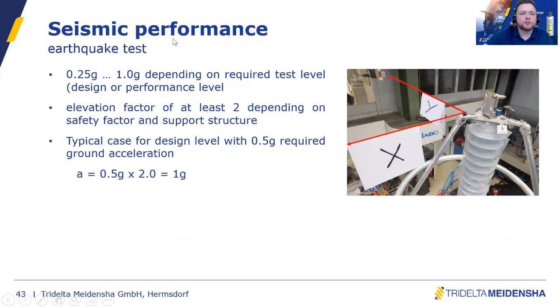Typically, this earthquake test is done with a ground acceleration between 0.25 G and 1 G, depending on the requested design or performance level. And we have to consider some factors, which are, let's say, security factors. At least we take 2. So we multiply the requested bottom acceleration by 2 or more. In a typical case, 0.5 G requested multiplied by safety factor 2, we will test 1 G bottom acceleration.